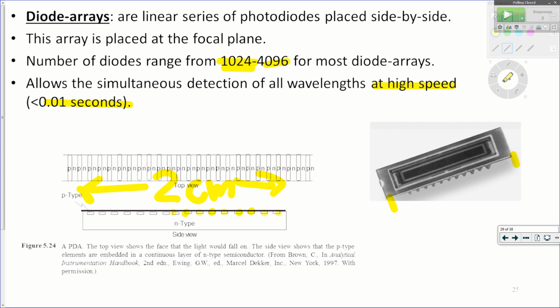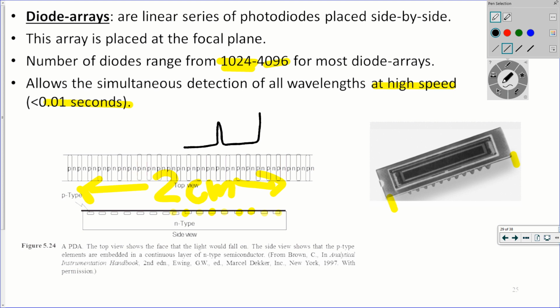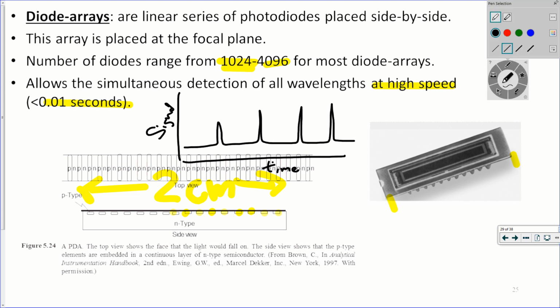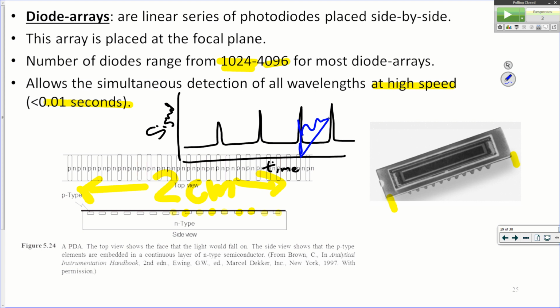So in an example, when we combine chromatography, where we separate components out as a function of time, we can get a separation of a signal at a given wavelength versus time. But also, if I have a photodiode array detector that's continuously doing a scan, at every point in time, it's collecting a spectra. So if I think about it in this time slice, there is a spectra for that component, right? And it's continuously collecting these spectra, and it depends on how fast your signal's changing.